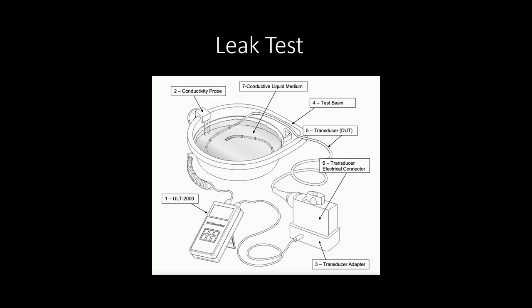One thing that we wanted to talk about was a leak test, because the most common reason early on when we started our program was that Central Supply would just say, hey, you guys sent two ultrasound probes down, two TEE transducers, and they failed the leak test, so we're not going to send them back up. They're broken. And we were like, what the hell is the leak test? The leak test is that they're testing the outside cover of the probe, to make sure the insulation is intact so they don't shock the patient.